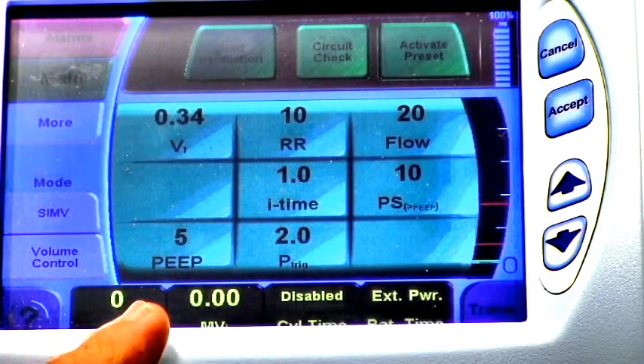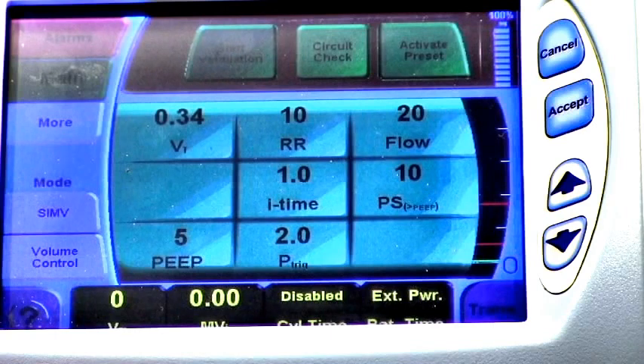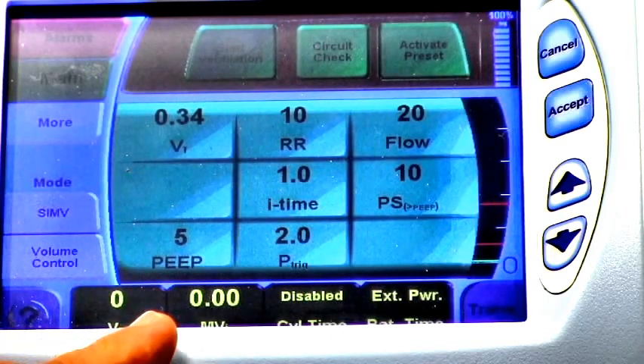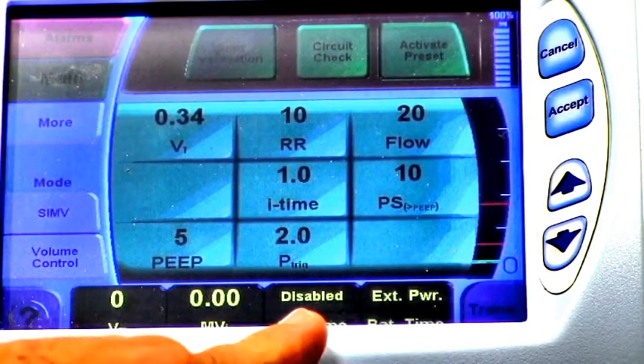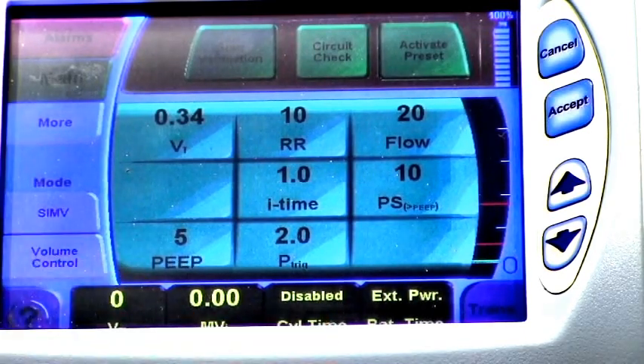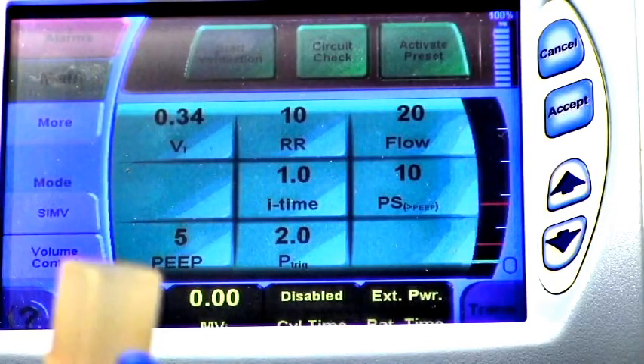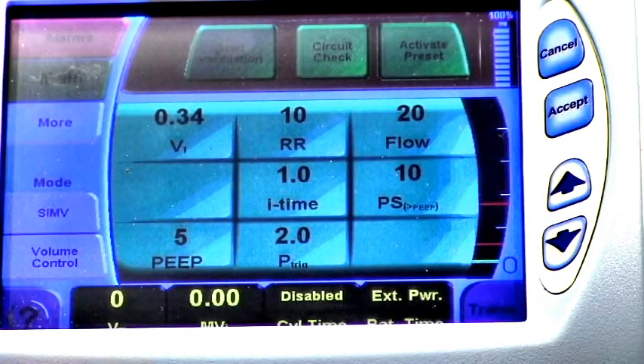Your PEEP, the average physiological PEEP for the normal adult, is between 3 and 5 centimeters of water, and for the average patient on our ventilator, we're going to have and maintain around 5. Your pressure trigger, even though it shows here 2.0, is actually negative 2.0. Basically what it says is when the patient is able to draw 2 centimeters of water pressure against this circuit, the valve will open and the patient will be allowed to take their own breath. And that is what allows the SIMV to be so much more interactively comfortable for the patient that is attempting to breathe on their own.